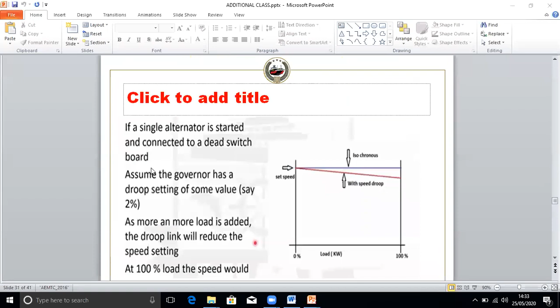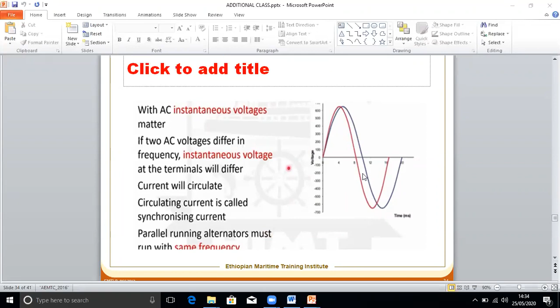You see in this here, AC instantaneous voltage. If two voltages differ in frequency, the instantaneous voltage at the terminal will differ, so a circulating current will flow. You see here what you can make out in this: the RMS voltage is the same. Both have the same voltage, but there is a phase difference, so this can cause circulating current. This is the phase difference. RMS voltages are the same. Peak values are the same.